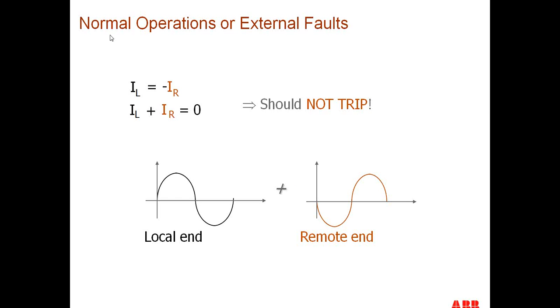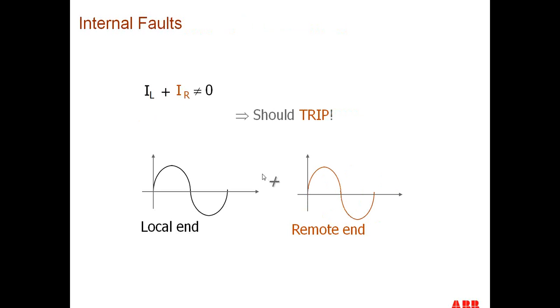So basically, for an external fault, IL is equal to minus IR, so the sum of the two, IL plus IR, the local plus the remote, is equal to 0, and the relay doesn't trip at all. Here we see the currents at the local end of the line and the currents at the remote end of the line. For an internal fault, the summation of the local current plus the remote current is not equal to 0, so therefore the relay should trip.